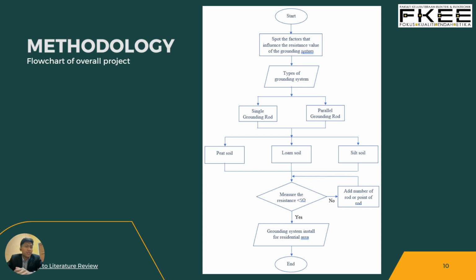The next part is the methodology, which is shown in the flow chart of the overall project. First, we need to spot the factors affecting the earthing system. There are 2 types of methods, each applied to all types of soils, and we measure it using an earth ground tester. If it is less than 5 ohms, the grounding system will be installed for the residential area. But if it is more than 5 ohms, we can overcome it by adding another rod.